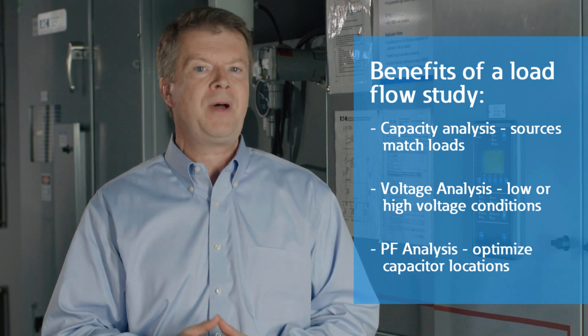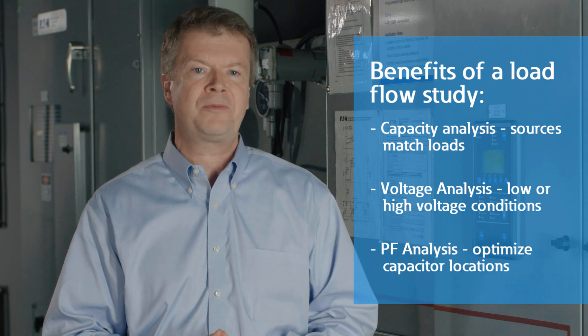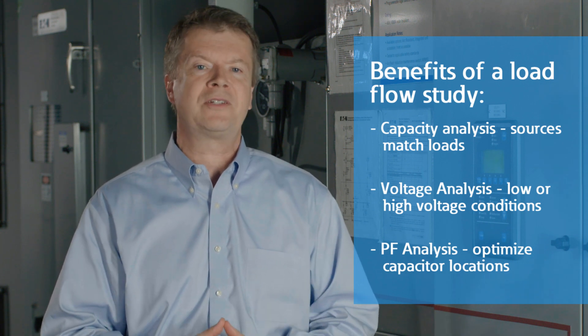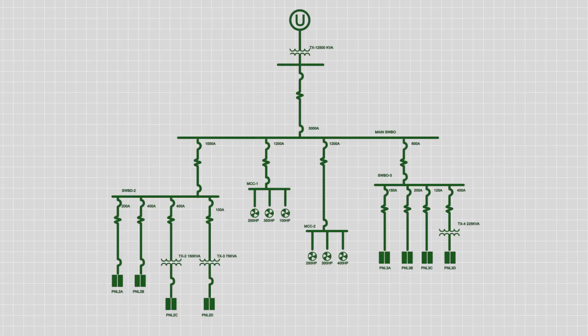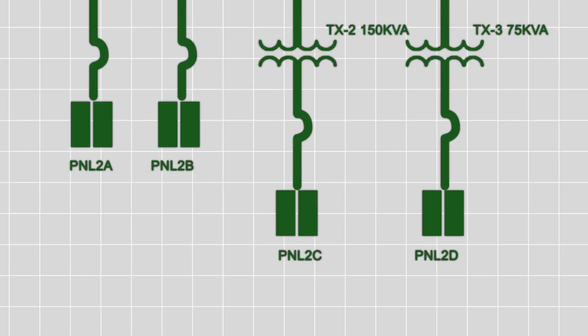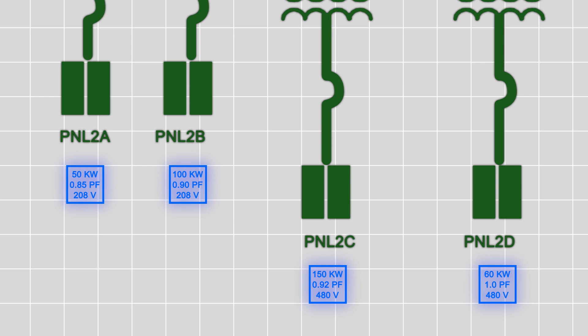Finally, a power factor study may indicate where capacitor banks are required to stay within the limits of your utility contract. The first step in a load flow study is to create an accurate system model and single line diagram. From there, today's computer programs can run simulations of that power system to evaluate what-if scenarios for load changes in contingent situations.